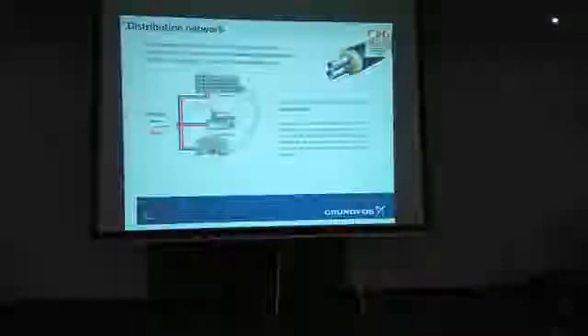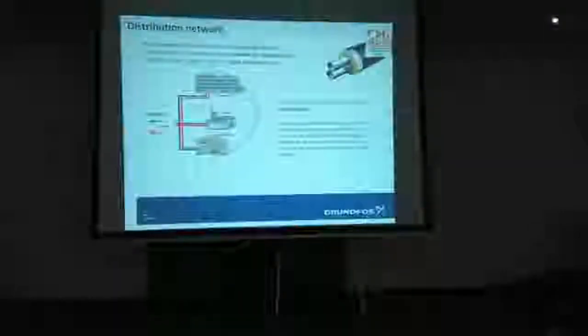You can group all these, loads of housing on one part of the network, through a series of plate heat exchangers, so you're working at a lower temperature in that area, and differential temperatures come into play because then it affects the resistance and the flow rates through buildings. Likewise with these, if you need a higher temperature, you can have a lower temperature from here, but put local power just to top it up at the last area where they want it, maybe for a process or something like that. Okay? And this mentions cooling, same sort of principle, it's just different temperature ranges. And here, in certain countries, we don't insulate the pipework at all, because it's already cold outside.